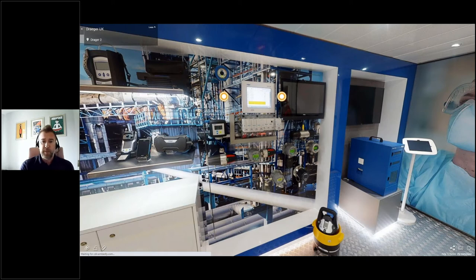Another new product for Dräger is the Polytron 8900. The 8900 is an ultrasonic leak detector, so this device listens for high pressure gas leaks, and again can be extremely useful in the early detection of leaks covering large areas of plant and assets, and is a really great supplement to point and open path detection for that reason.